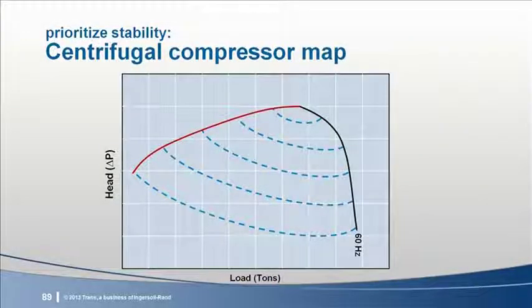A second and more common stability issue is unstable condenser water temperature control loops. It seems these occur quite often with no one concerned with the impact on equipment or system performance. Let's examine a couple examples of why stable control needs to be a priority in variable speed chiller plants. Shown here is a simplified version of a centrifugal compressor map. The horizontal axis is load, and the vertical axis is head or lift. On the right, the compressor map is bounded by the black capacity line.